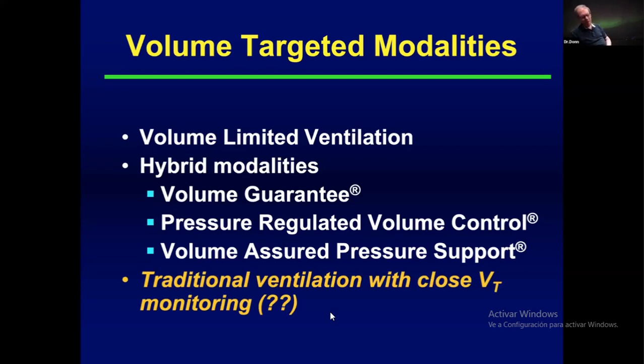And finally, there is traditional ventilation with close tidal volume monitoring. And over the years, I've often been asked the question, well, we don't have a volume monitor, we don't have a volume-targeted device. What if we just used our time-cycled pressure-limited ventilator and paid really close attention to the delivered tidal volume and adjusted accordingly? Well, I think you should be doing that anyway, no matter what type of ventilation you're providing. The problem is that you cannot adjust as quickly as a computer. And you're also making your adjustments post facto, after the breath has been given. So it really is not a very satisfactory way of delivering volume-targeted ventilation.